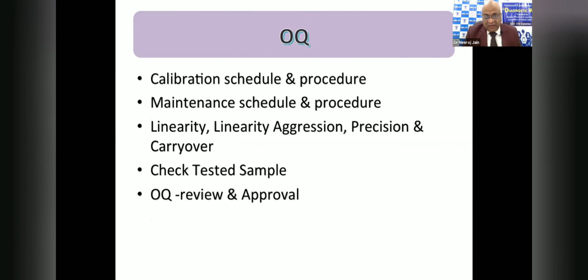In operational qualification, you are defining the calibration schedule, you have a documented calibration procedure, and you are following that procedure. Whatever maintenance schedule you have discussed with the company people, you have prepared a format for that, and you have a procedure for how to carry out all the maintenance checks. So you are following it and keeping records of all these things. Then linearity, regression analysis, precision, carryover: you have a documented procedure to carry out all these things, because they are big topics in themselves, but all are important to be checked in all the machines where they are applicable.